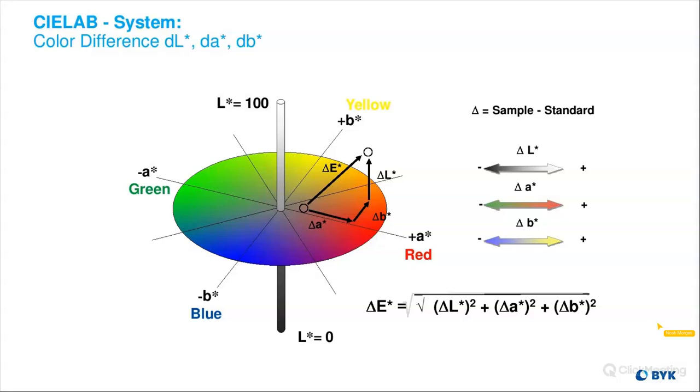And you see, what delta E 2000 does is it'll figure out where you are in color space. So if you're in the red region or if you're in the green region, it'll make that tolerance smaller or it'll make that tolerance bigger, depending on what color you're actually looking at. And so if I'm looking at a red and using delta E 2000, my tolerances are physically going to change to make them a little bit tighter so that I'm not accidentally failing samples, or vice versa. And so that's really what the equations go into.